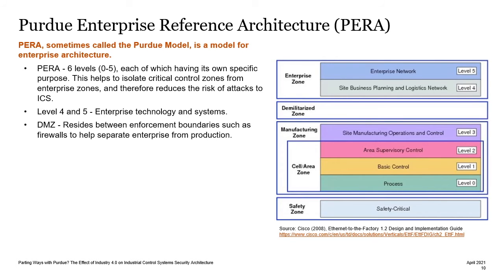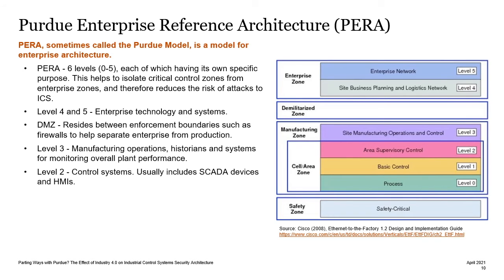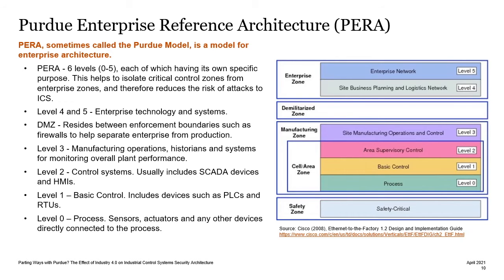Between levels 4 and 3 is the demilitarized zone, which often resides between two firewalls. In level 3, you'll find manufacturing operations and systems such as historians, and also systems for monitoring overall plant performance. Level 2 contains the control systems, which usually include SCADA devices and HMIs. Level 1 is the basic control level, where we have devices such as PLCs and RTUs. And then at level 0 is the process itself, with sensors and actuators, or anything else connected directly to the process.